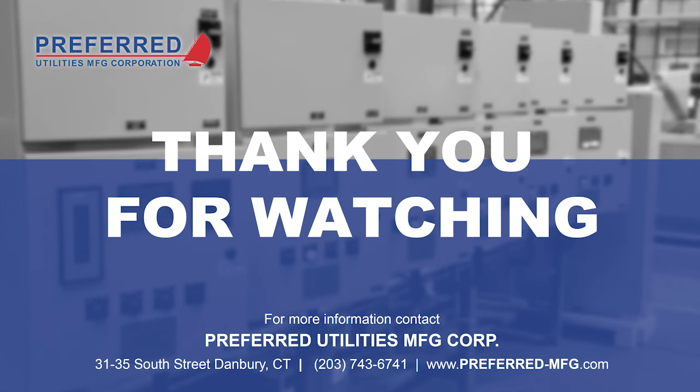Next question, what are the concerns when utilizing boiler heating oil as emergency generator diesel fuel? Boilers are a lot less sensitive to different fuels than diesel engines are. On Preferred's burner side, we make burners that burn a wide variety of liquid fuels. But the most common fuel you're going to see for boilers is number 2 diesel, and that's the exact same thing that's used in the gensets. I would not burn anything but number 2 diesel in your genset without checking with the engine manufacturer.